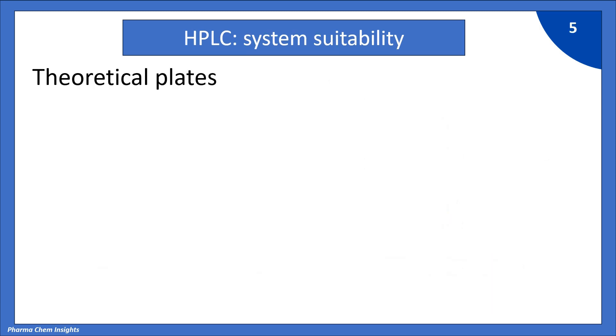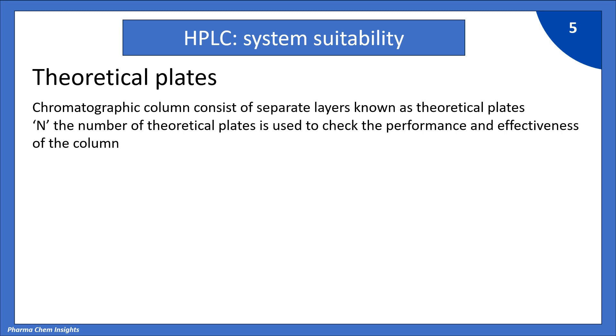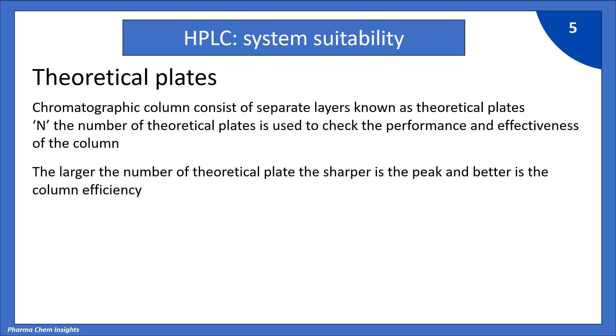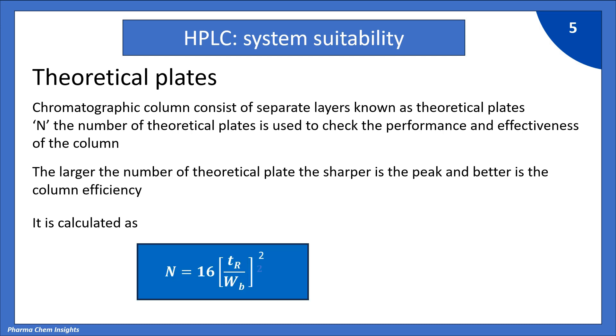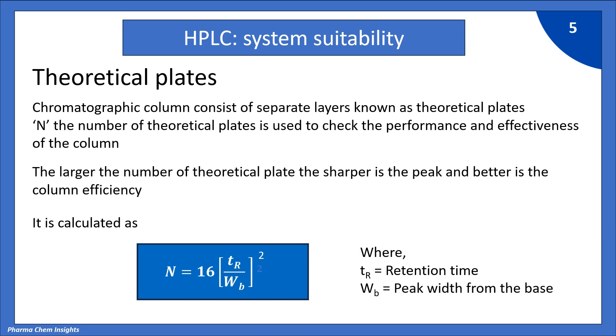Next parameter: theoretical plates. A chromatographic column consists of separate layers known as theoretical plates, and the number of theoretical plates is used to check the performance and effectiveness of the column. The larger the number of theoretical plates, the sharper is the peak and the better is the column efficiency. It is calculated as N = 16 × (TR / WB)², where TR is retention time and WB is peak width from the base.